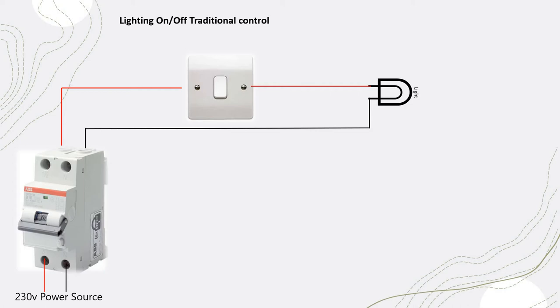Moving on to the wiring part, we start with the traditional lighting control. Everyone has seen this conventional switch in every house — this is a one-gang switch controlling only one light. From the electrical distribution board, you take the live wire to the switch, and from the switch the live goes to the light. The neutral is pulled directly to the power source, so you're controlling the on/off of the light directly through the switch.